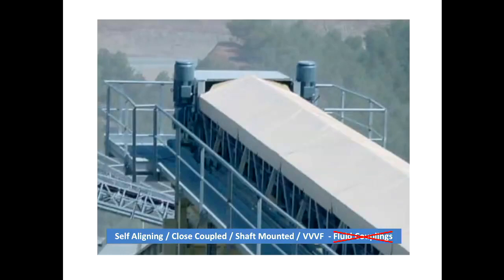Okay, here's some motors. I put this in because I like the self-aligning motors. You don't have to worry about couplings and all this kind of stuff. They're shaft mounted. You've got a tight connection between the motor and the gearbox to keep the dust out.